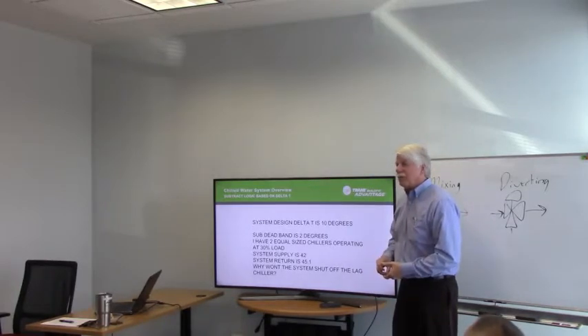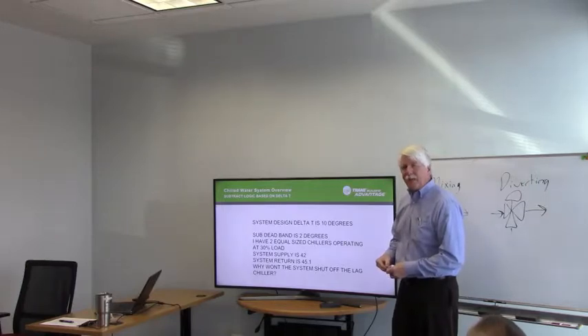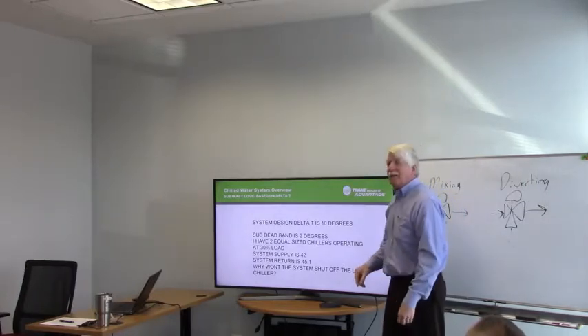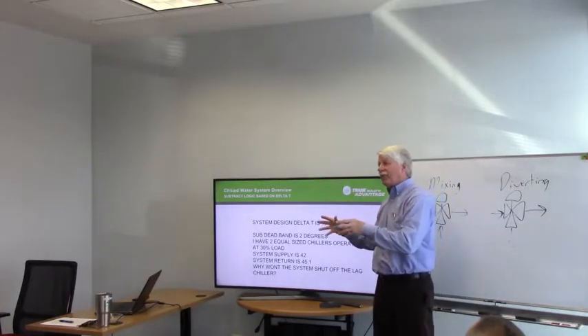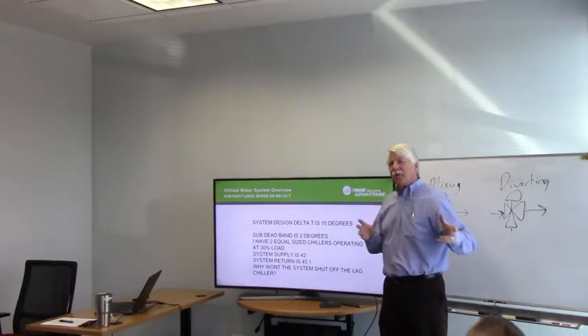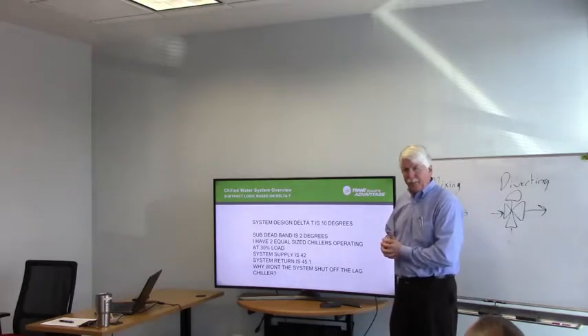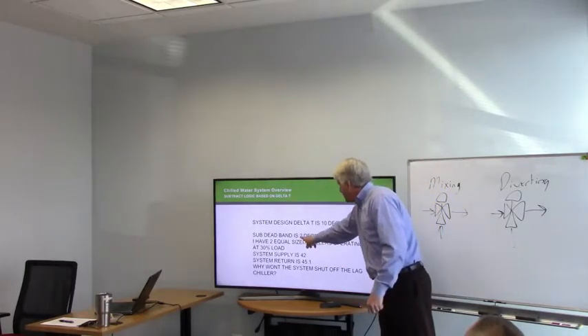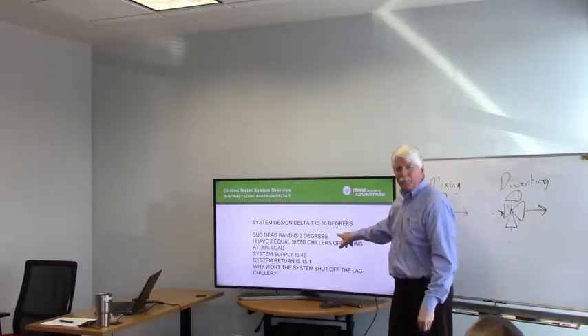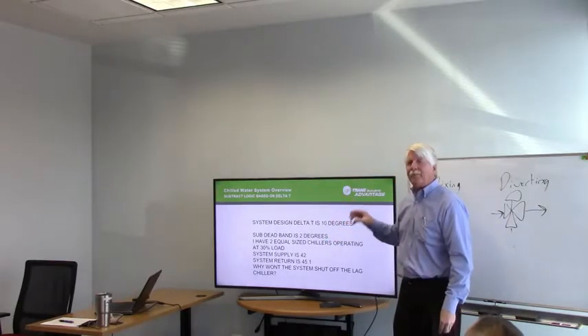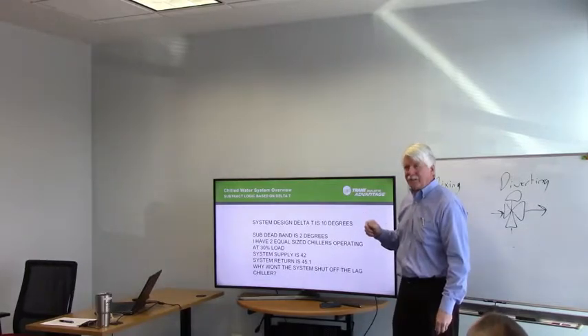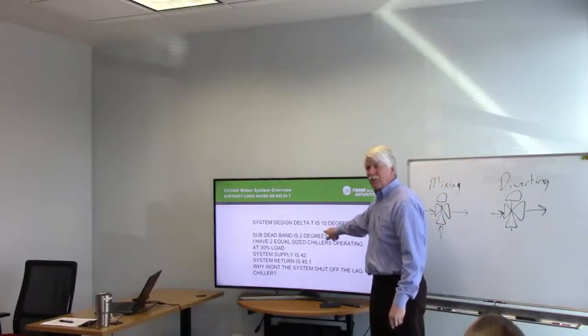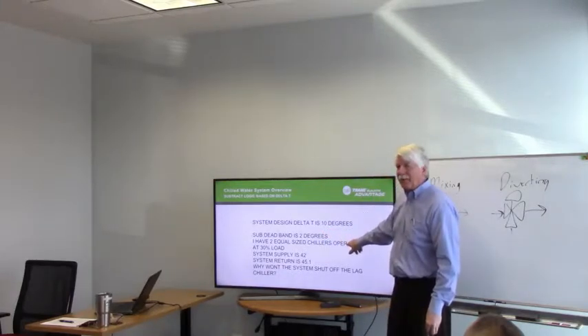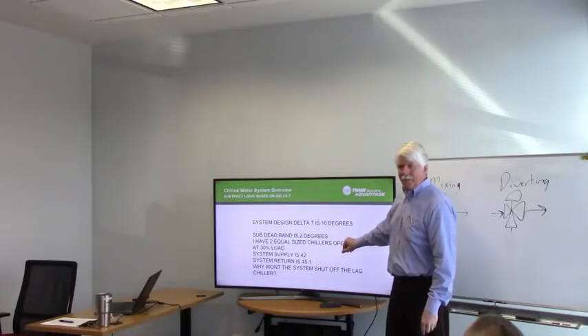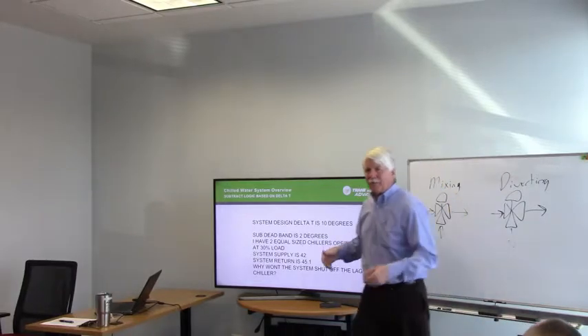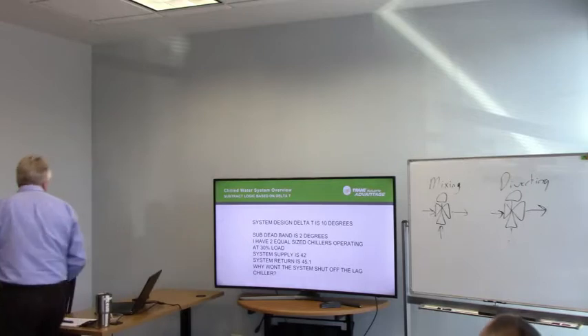Now, the reason I bring this up to you guys is one of the most common complaints we have on chiller plant control is after we've had a peak and we've got multiple chillers running, the lag chiller doesn't want to turn off. And that's always because of this number and this number. What I've found is that most of the time the design engineers are wrong on their delta T. They design the system on 10 degrees, but a lot of times they operate at like 8 degrees. And so you'll never get the delta T you need to get it to turn off.